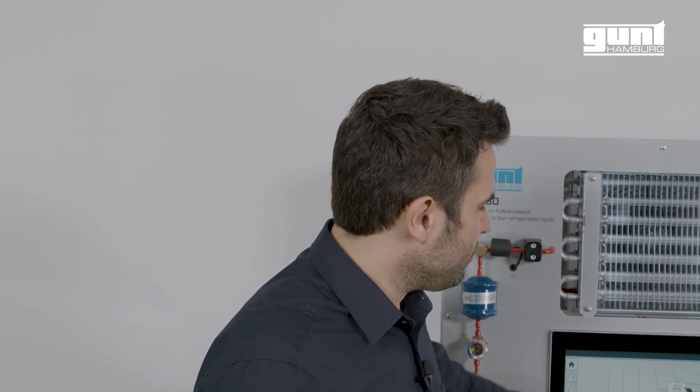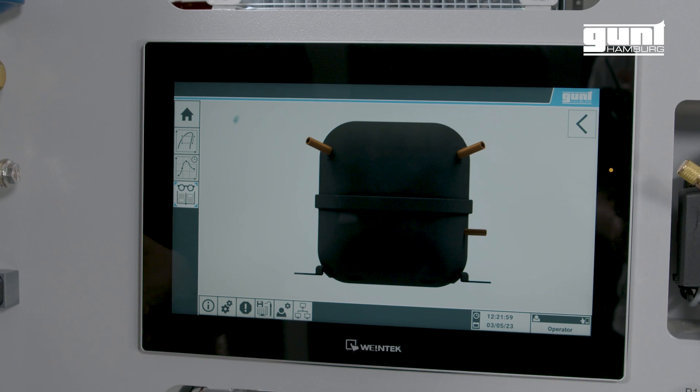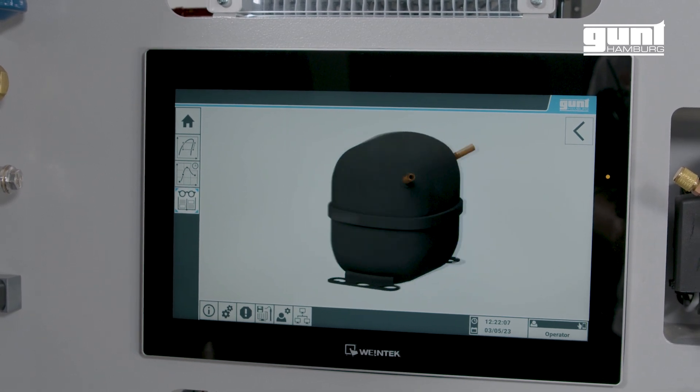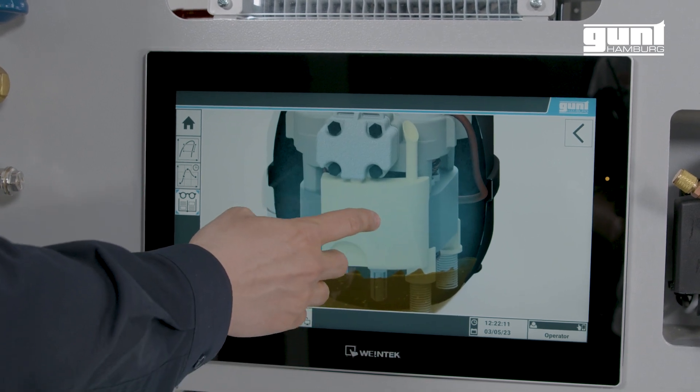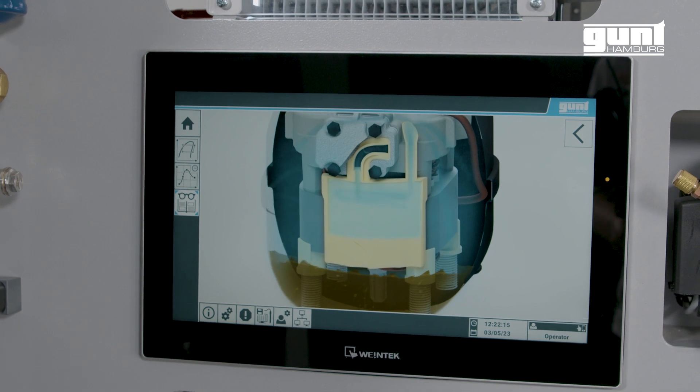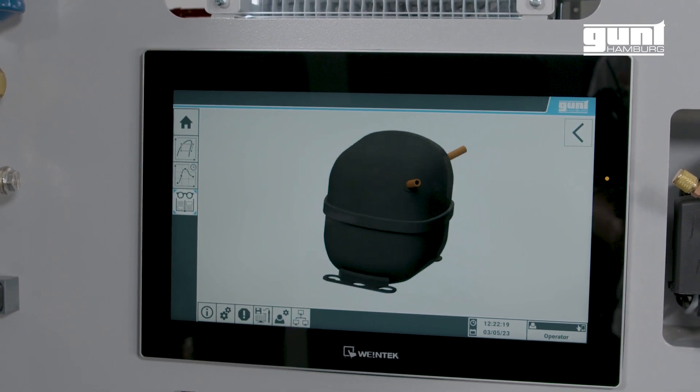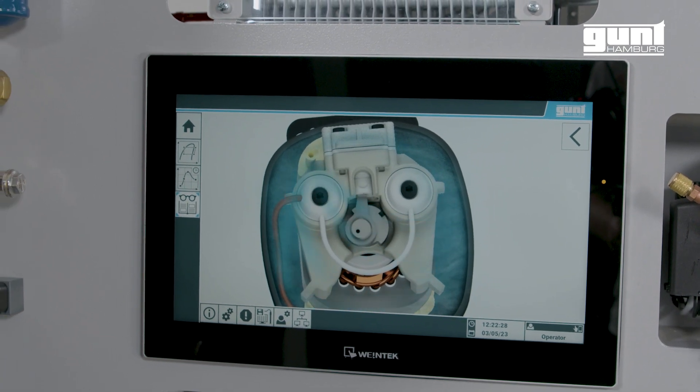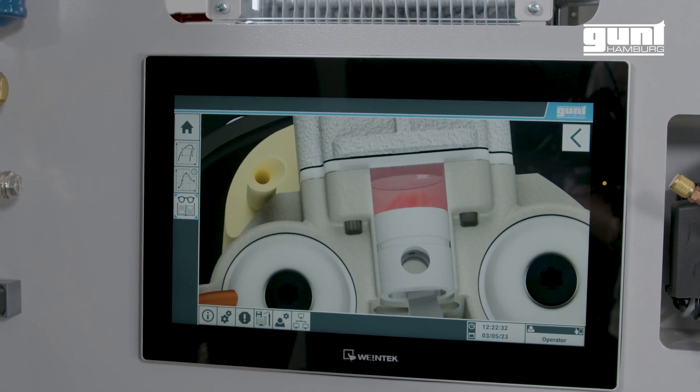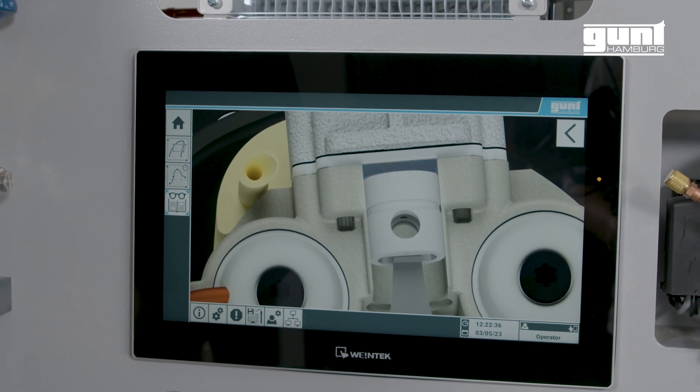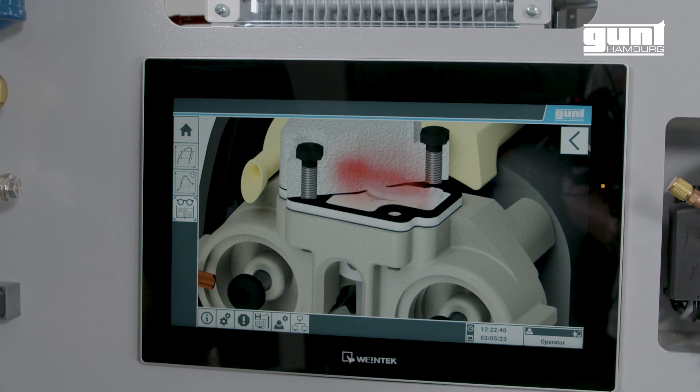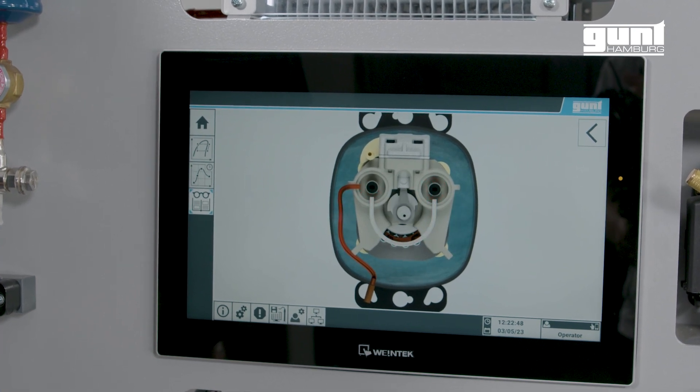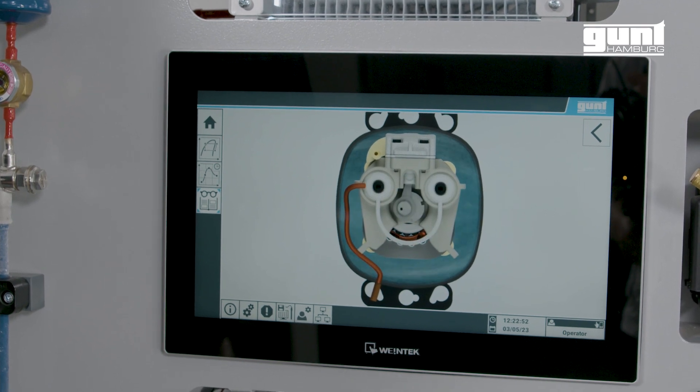Let's follow up with the compressor. What you can already see is that it is working in the fully gaseous phase. The blue low pressure gas is sucked in and it's expelled again on the high pressure side in red. When you want you can just pause the video and discuss the details with your students in a dialog. If we look at the compressor from above we see the rotating shaft and the working pistons. If we go a little deeper we can see the suction valve. These are designed as simple reed valves. And there's also a reed valve on the high pressure side. Then in the last step we can see how the pressurized gas flows through the pulsation damper which also works as an internal heat exchanger.